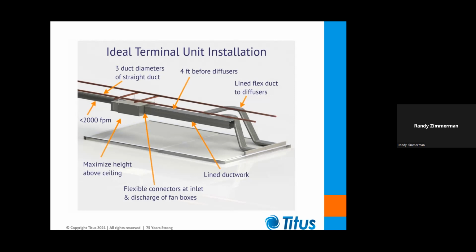Sometimes I get asked about spring isolators. Spring isolators aren't absolutely necessary to good terminal unit performance. The boxes are actually tested hung rigidly. That doesn't mean the spring isolator won't provide good insurance for unforeseen job site conditions. So they're still a good idea. They're just not absolutely necessary. Sometimes it's a good idea, especially on fan-powered boxes, to provide flexible connectors at the inlet and the outlet to break up any duct or terminal unit vibration.